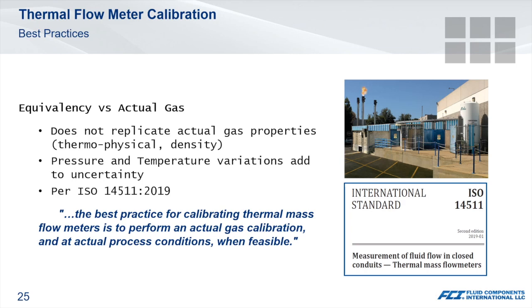The use of inferred variables in flow measurements is commonly overlooked. This is when a density is assumed without the meter technology being tested on a traceable calibration stand. To save costs, an air calibration might be performed with a linear correction factor applied to offset the differences in the gas densities. Depending upon the technology, these equivalencies don't necessarily account for thermal physical properties of hydrogen, such as absolute viscosity, specific heat, and thermal conductivity. Changing process conditions are not always accounted for when a density is assumed, leading to an incorrect measurement of the actual mass of gas being measured.